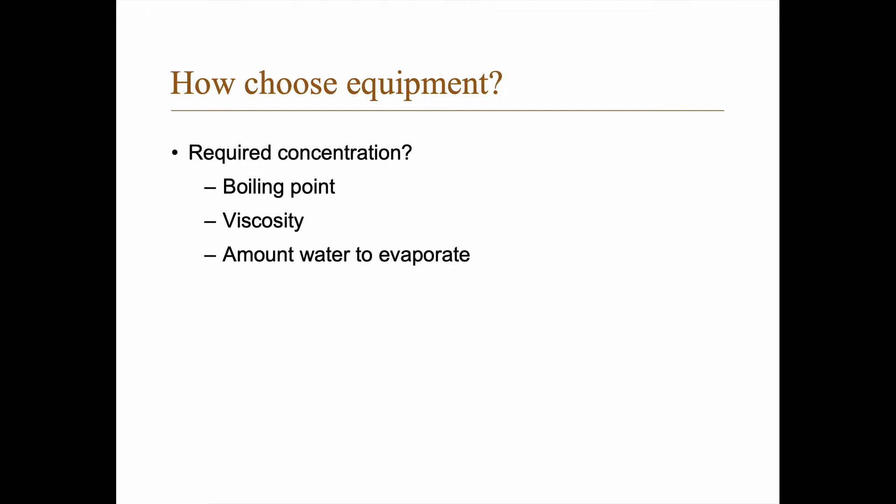One thing to consider is the required concentration, and with that comes the boiling point, the viscosity, and also the amount of water you need to evaporate — whether you only need to evaporate a tiny amount or almost everything. Some liquids foam, and if you have foaming there is a risk for entrainment, where tiny droplets follow the vapor flux out, which is not good because you get solids in your vapor flow.